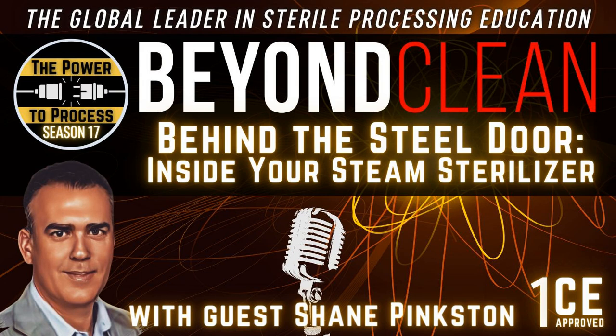One — don't overload your sterilizer beyond what it can do. The key is ensuring you have enough room around your goods for steam penetration. I typically teach the two-finger rule: if you can put two fingers between a pack and another pack, you probably have enough room. If they're much tighter than that, you might risk steam penetration into the load. So that's a big piece of it.